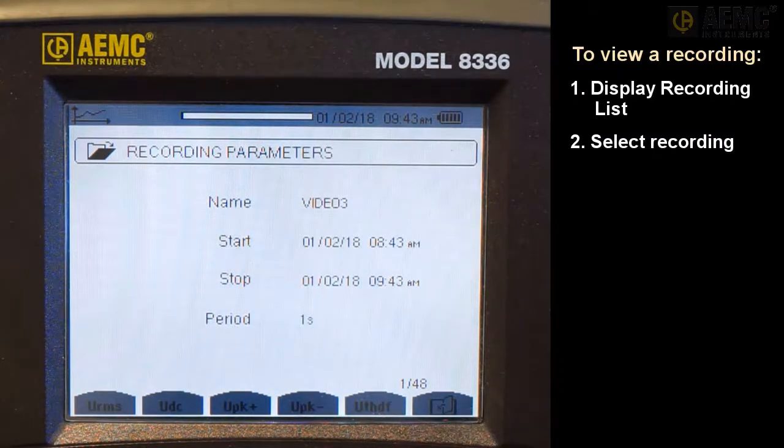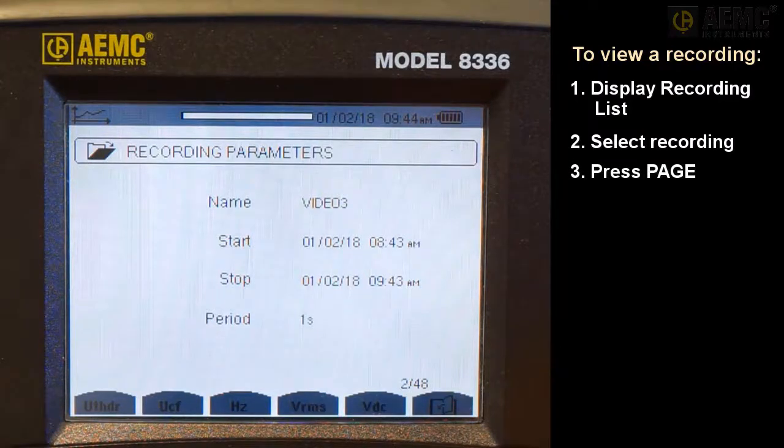The first page of the recording shows basic information, including the recording name, the start and stop times, and the sample period used. In the lower right corner is the page number, which in this example, indicates we are looking at the first page of a 48-page recording. The number of pages is determined by the number of quantities selected in the Trend Configuration screen. Press the Page Function button on the far right to cycle through the pages. As you do this, the remaining Function buttons refresh, to correspond with the data contained on the selected page.